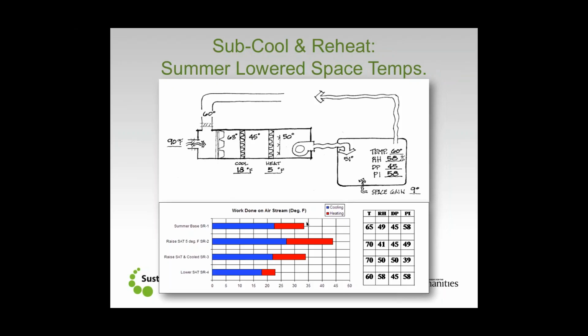This isn't going to work everywhere, but it might work in a library or archive storage area, especially in the summertime. And here's an option, right? If we still do that 45-degree dew point, oftentimes the best way to save energy when it comes to summer operation in a subcool and reheat system is to ask ourselves whether or not we can lower the space temperature in order to do less reheat.